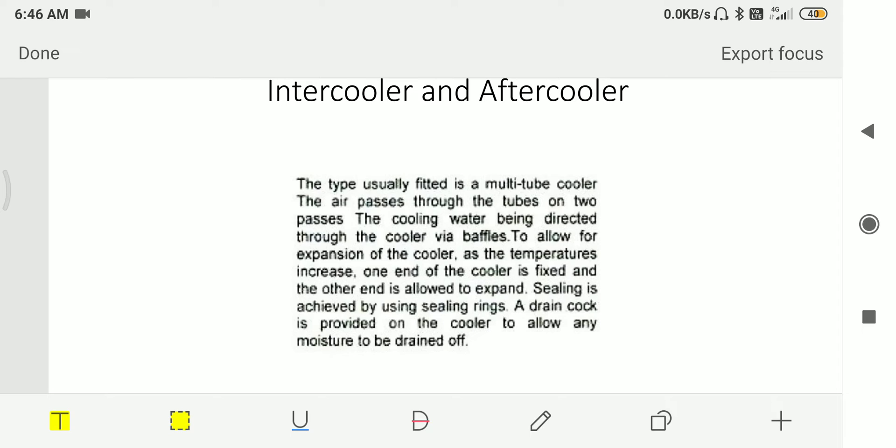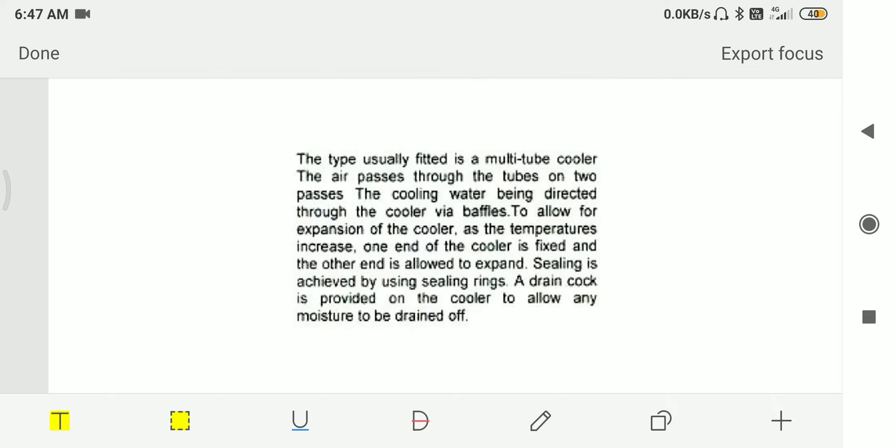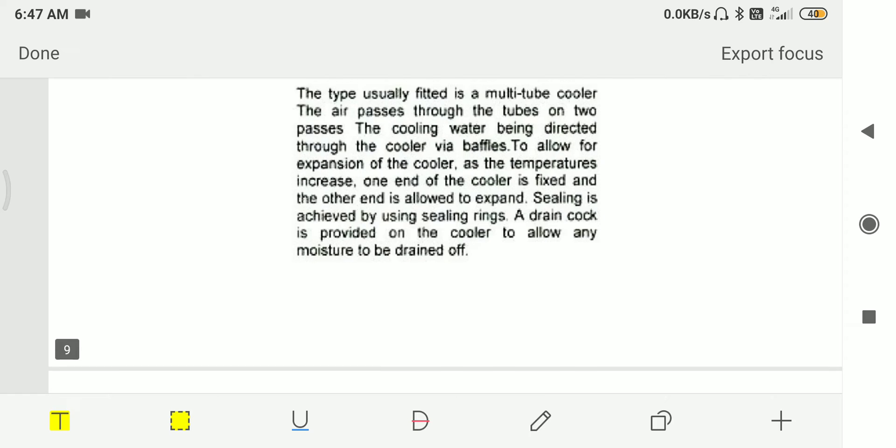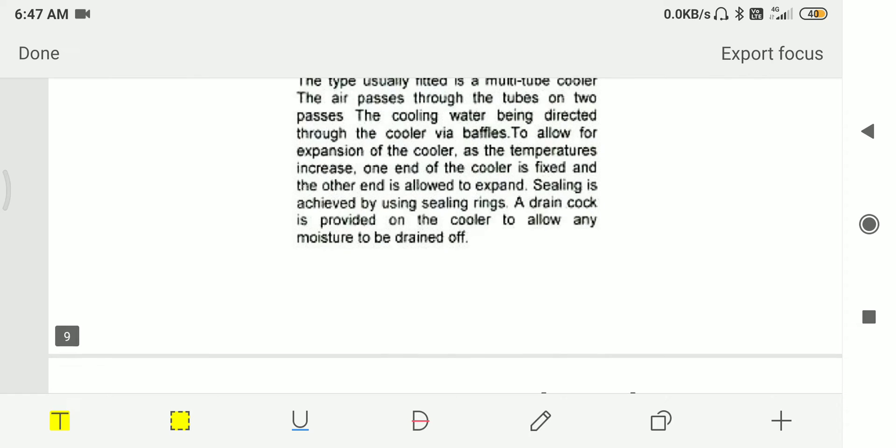The type usually fitted is a multi-tube cooler. Air passes through the tubes in two passes, with cooling water being directed through the cooler via baffles. To allow for expansion of the cooler as temperature increases, one end of the cooler is fixed and the other end is allowed to expand. Sealing is achieved by using seal rings. A drain cock is provided on the cooler to allow any moisture to be drained off.